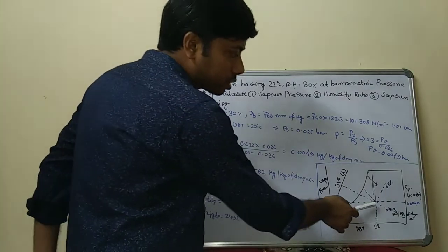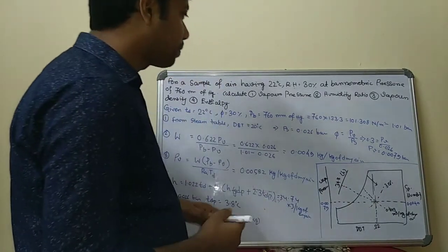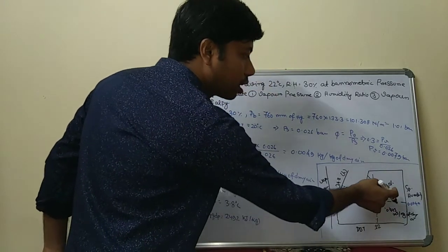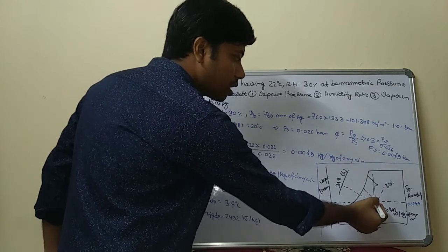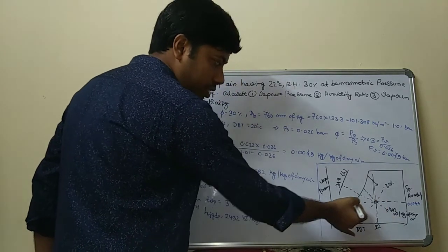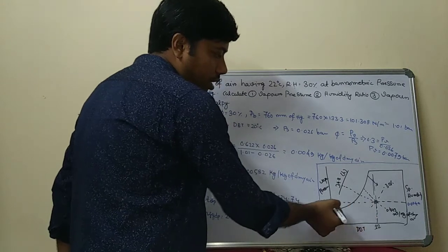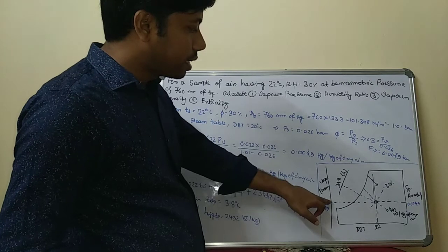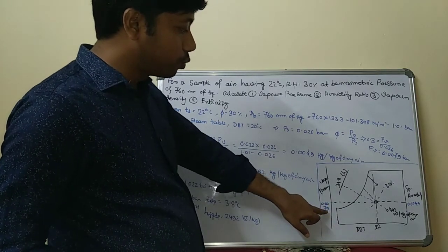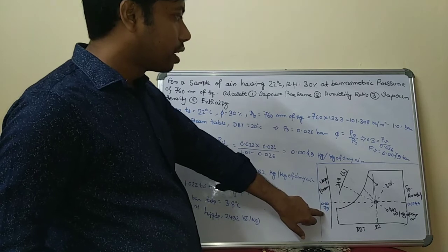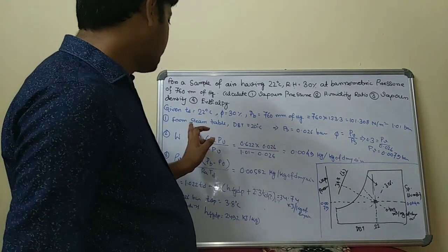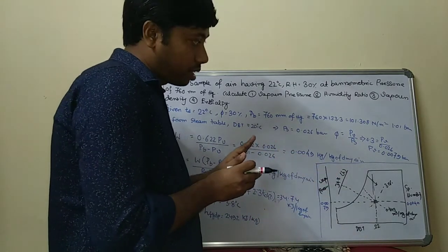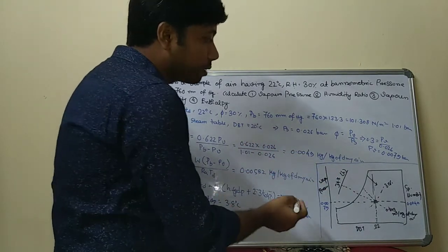So corresponding to this cutting point, you can calculate the vapor pressure. First you have to calculate the vapor pressure. This is your meeting point of relative humidity 30% and dry bulb temperature 22 degrees Celsius. If you draw this line horizontally in this way, in the left part of your chart, it will give you the line which cuts your vapor pressure, that would be 0.0079 bar, which is basically calculated by using a formula, but you can calculate the value easily from this chart.